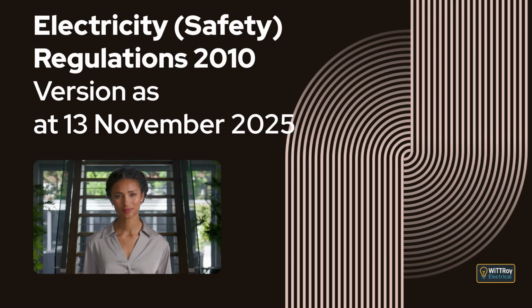This regulation explains that a person may inspect high-risk prescribed electrical work only if they are authorized to inspect high-risk prescribed electrical work, or, where the work was carried out under an employer license, if they are authorized to inspect the work under the employer's system of operation. It then explains that a person must not inspect prescribed electrical work if they personally carried out the work, supervised someone else carrying out the work, or issued the certificate of compliance for that work. Reg 72 Record of inspection. This regulation explains that a person who carries out an inspection of high-risk prescribed electrical work must prepare a written record of the inspection.